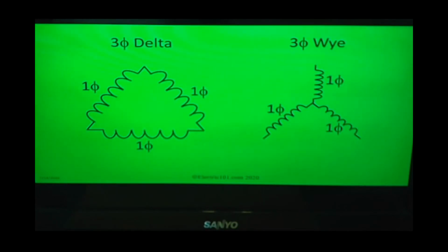Now, the most common type of transformer you see in industry is the three-phase transformer. Here we have 1, 2, 3 single-phase transformers. Those single-phase transformers are joined together, and they form what's called a delta. So this is a three-phase delta transformer. That's common. Another method to create a three-phase transformer is called a Y. The same individual three phases, 1, 2, 3, are joined together at one point. This is now called a Y transformer. These two would be the most common transformers you could ever come across. One side would be the primary windings, the other side would be the secondary windings.